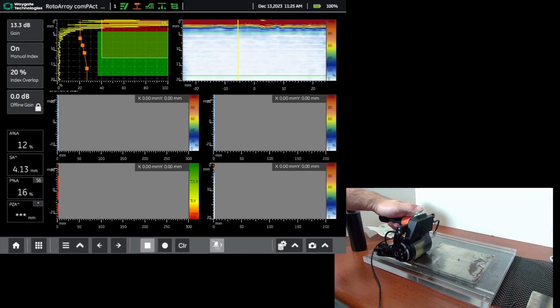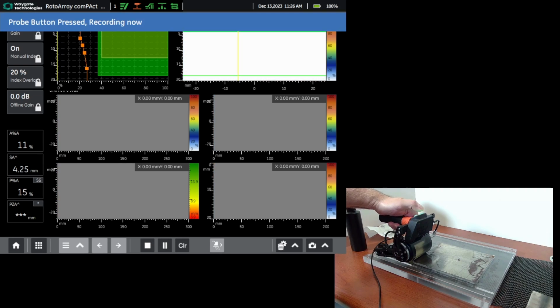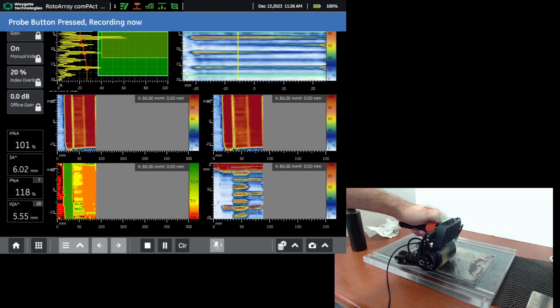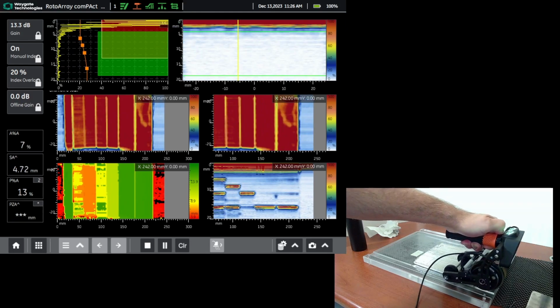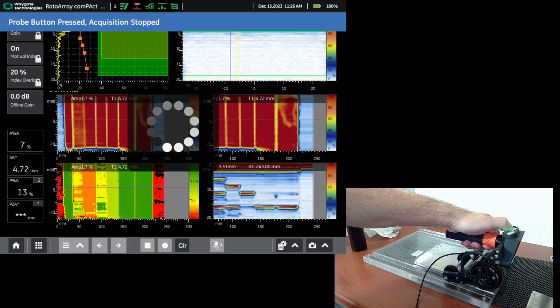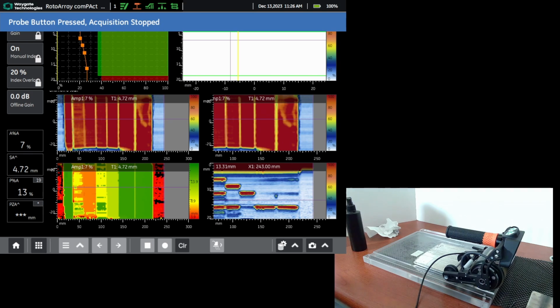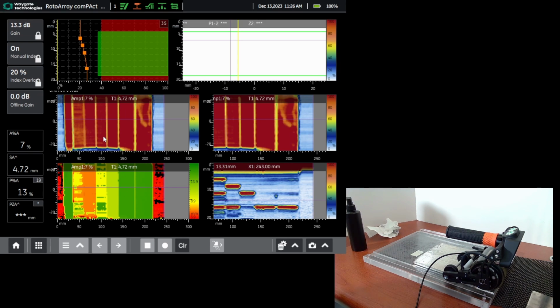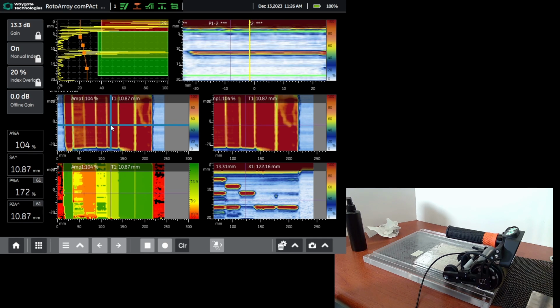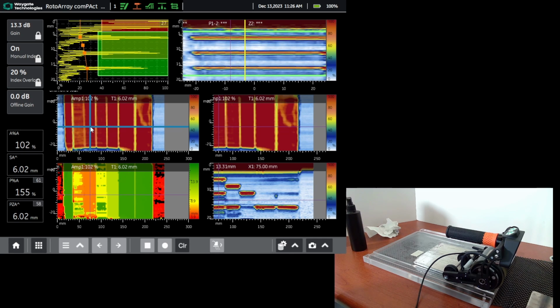With our time-corrected gain curve recorded, we're ready to do a scan. So I'll hit the start button on the RotoArray, run down the length of the block, do stop, and now we can take a look at our scan. So just doing a quick analysis, my overview C-scan here on the top is an amplitude view. So if I look through that, each one of those steps is going to come out to be about the same amplitude. They are actually saturated.